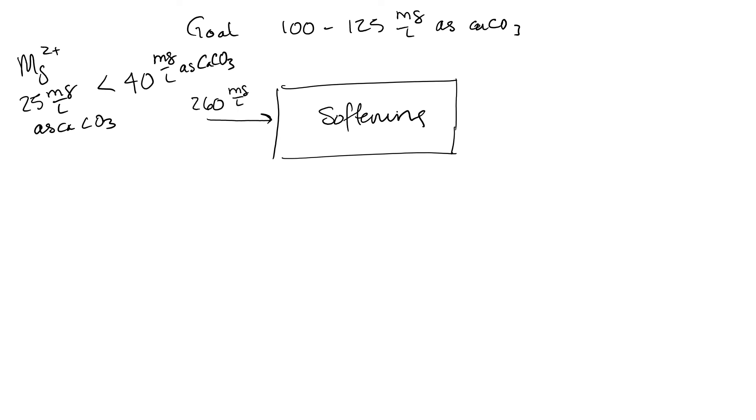So again, we're starting 260 milligrams per liter as calcium carbonate. Now, if we only remove the calcium plus neutralizing the CO2, then we have 30 milligrams per liter as calcium carbonate for our calcium. Our blend is still the same, 260 milligrams per liter as calcium carbonate. Our mass balance is still the same, around that same point.